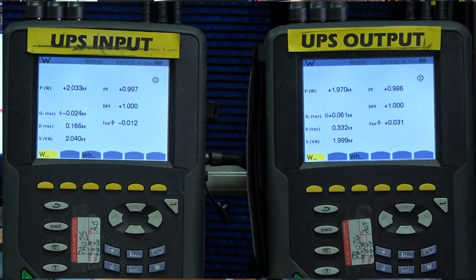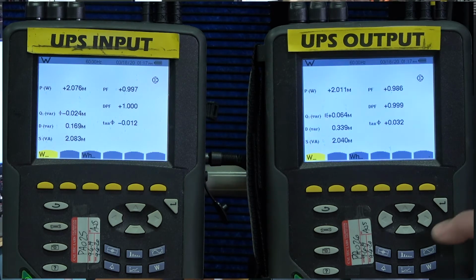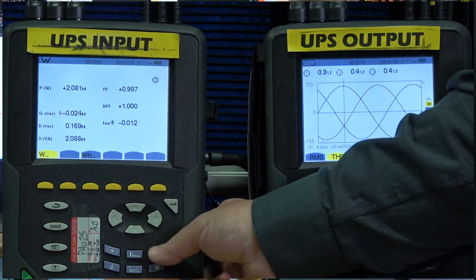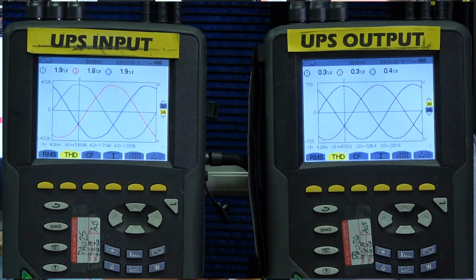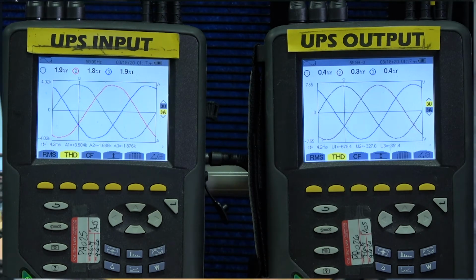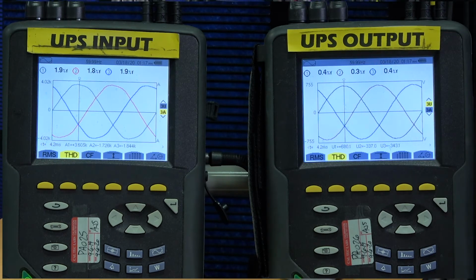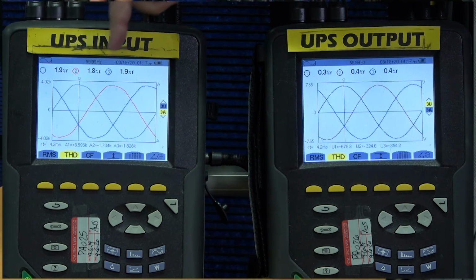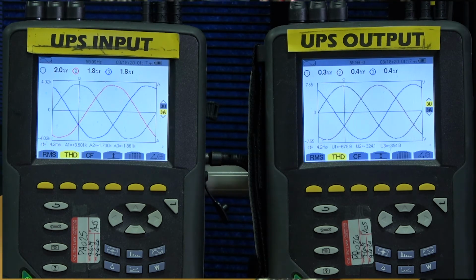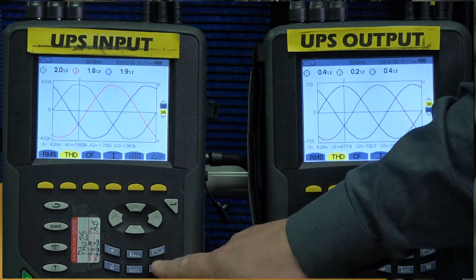Next, we're going to increase our load to 2 megawatts, so 100% load on the UPS. Now that the load is at 2 megawatts, we'll look at the output voltage harmonic distortion, still about 0.4, 0.3% on each of the phases. We'll also look at the input current harmonic distortion, let's say about 1.8 to 1.9% input total harmonic distortion of the current. Again, very low and well within spec on the UPS.